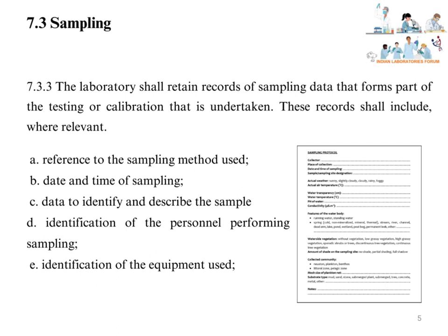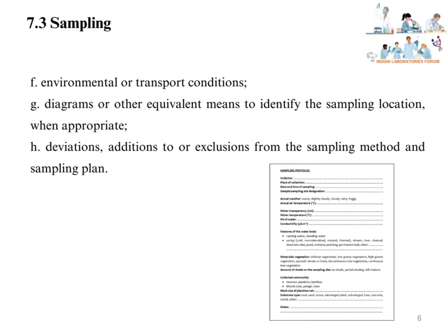Records shall also include: identification of the personnel performing sampling, identification of the equipment used for sampling, environmental or transport conditions of samples, diagrams or other equivalent means to identify the sampling location when appropriate, and deviations, additions to, or exclusions from the sampling method and sampling plan. All these details should be available in the sampling record, and records should be retained as per the laboratory-specific retention policy.